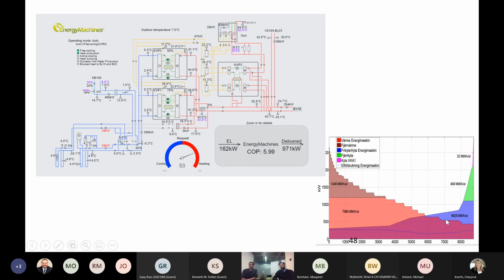Where it gets really interesting is this purple part at the bottom, because it means we have a cooling demand at the same time as a heating demand. Then we don't even need to use the storage - we simply let the energy pass through the system using the heat pump. It's simply a matter of taking waste heat at a lower temperature, upgrading it, and delivering it as valuable heat on the other side of the system.